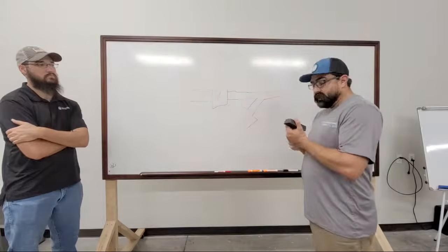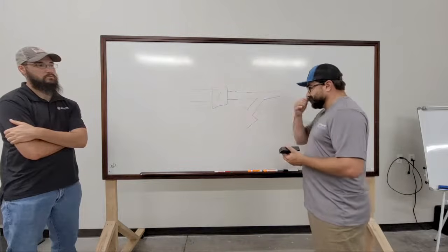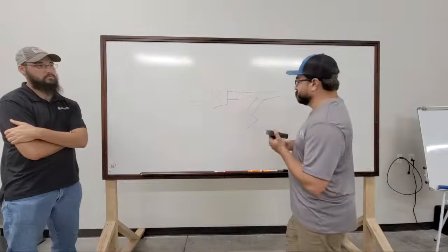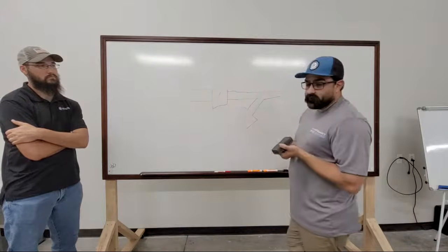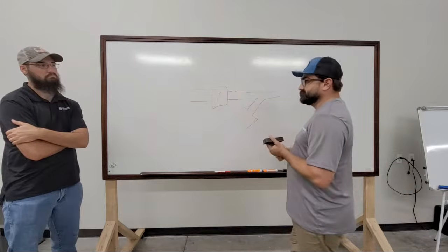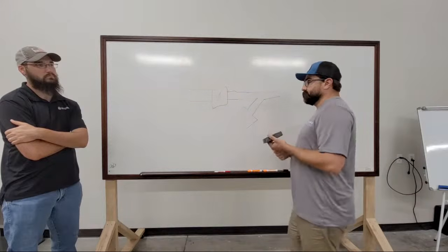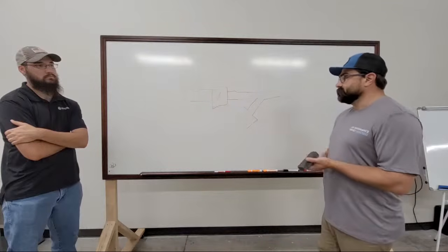So that happens a lot. It's a way to retrofit in a fan power box, I guess. It's not really the greatest, in my opinion, but it works. We've got quite a few buildings that are set up that way. It's the same exact function as a complete factory-built fan power box. It's just 2 separate pieces.